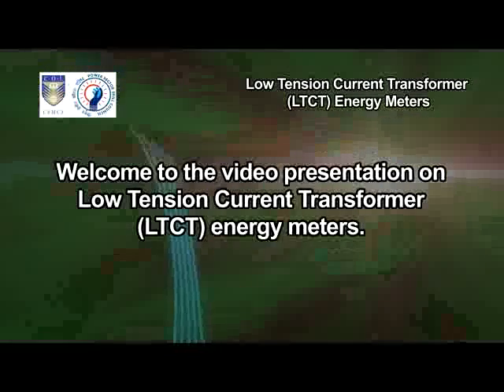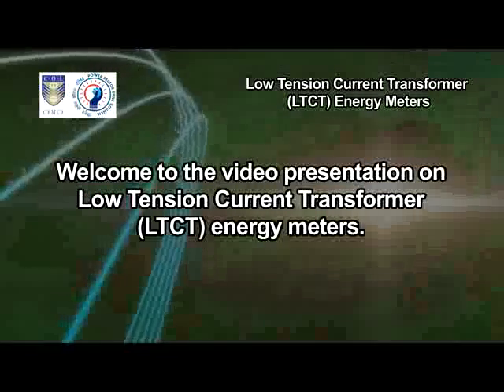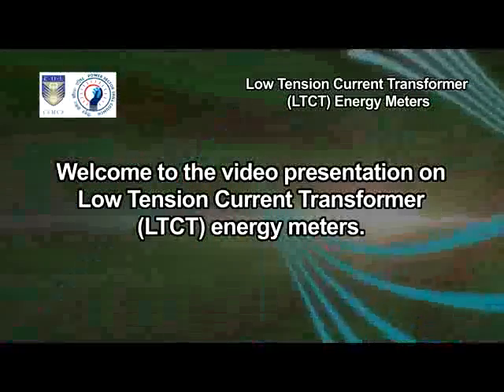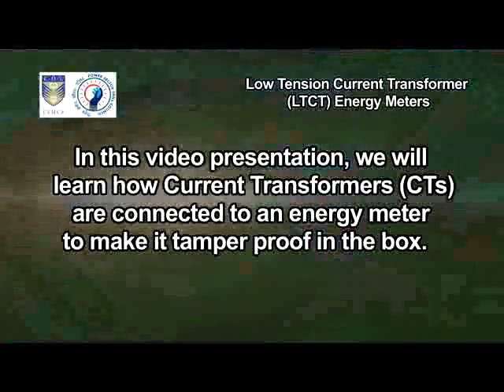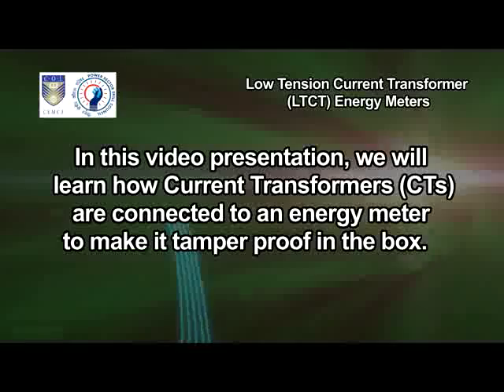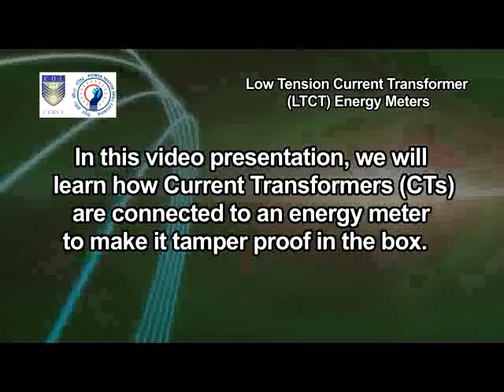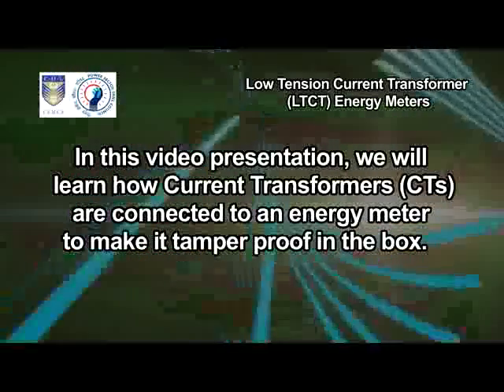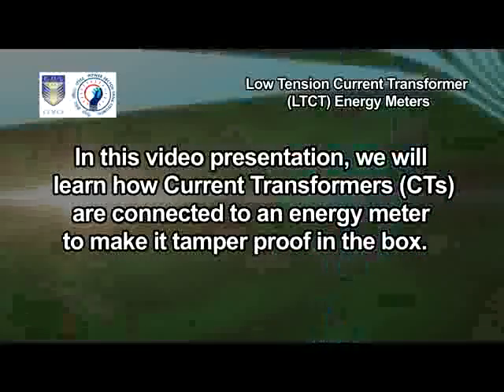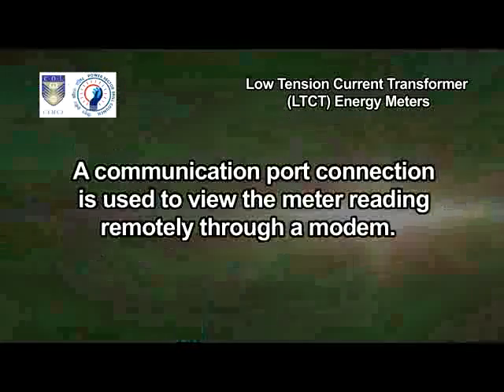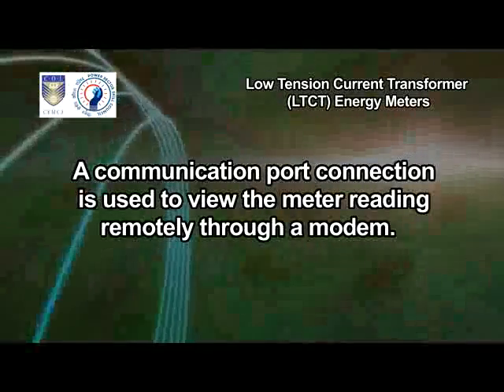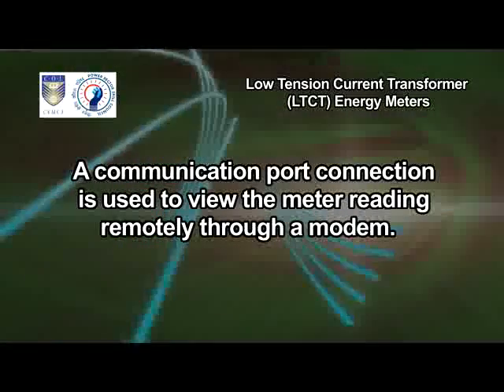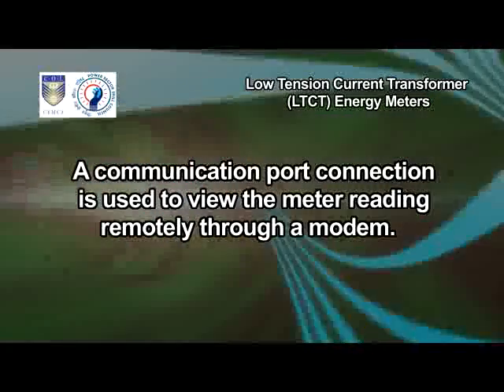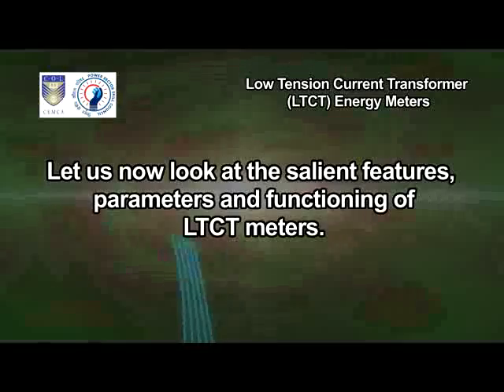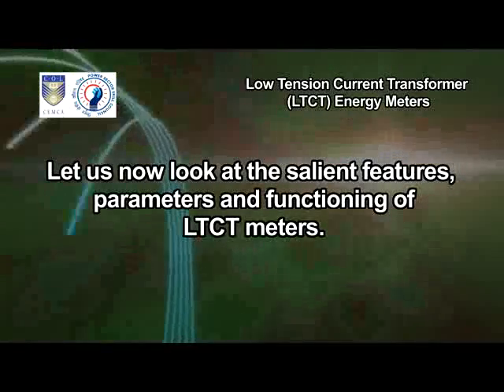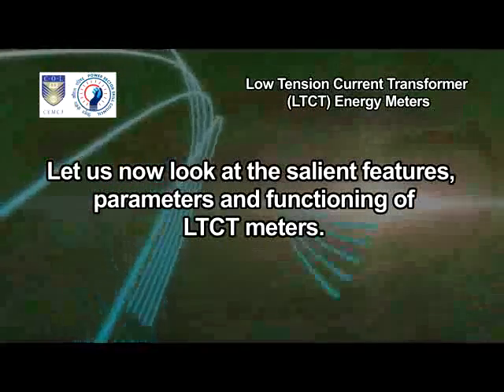Welcome to the video presentation on Low Tension Current Transformer LT-CT energy meters. In this video presentation, we will learn how current transformers (CTs) are connected to an energy meter to make it tamper-proof in the box. A communication port connection is used to view the meter reading remotely through a modem. Let us now look at the salient features, parameters and functioning of LT-CT meters.